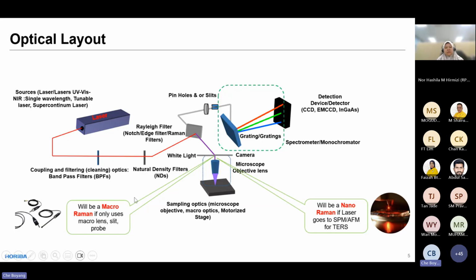However, in some cases, you may not have the microscope with you. For example, if you're using a handheld Raman or a probe-based Raman, we call this a macro Raman. It means we just use the light spot to interact with your sample, and we don't have very fine control over this light spot. So you can still get the spectrum of your sample, but you will not be able to get a lot of spatial information about your sample. In some cases, we can also replace the microscope with an atomic force microscope, or AFM for short, which further increases the resolution of your Raman result, and we can reach down to the nanometer range. Then we call this nano Raman. So based on the sampling optics we have, we can have either micro Raman, macro Raman, or nano Raman.